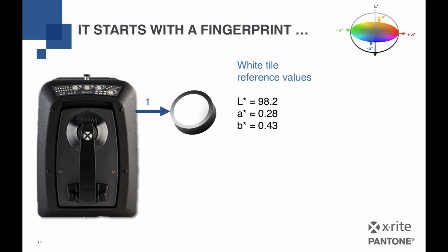your white tile, which comes with every color measurement instrument, has a set of reference values. A white calibration is required because the light source you use in an instrument also has a specific spectral emission distribution, and we need to neutralize it to 100% level in order to allow a relative spectral measurement, which then converts into these LAB values. So if you have a white tile with reference values, and you perform a calibration and make a check measurement after the calibration, that white tile would ideally read exactly those reference values, because any minor variation of the instrument condition is compensated away with that calibration procedure, so that the white tile after a calibration reads very closely to those values which are referenced on it.